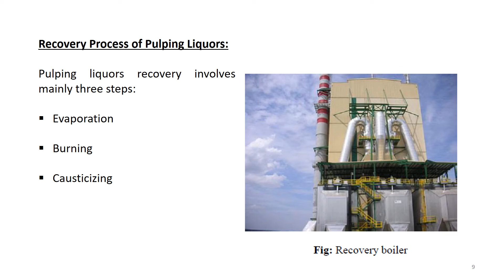As we have discussed, in the recovery process, or regeneration of pulping liquors, one of the main processes involved is evaporation. In the kraft process, weak black liquor is separated from the pulp by washing and sent to the kraft recovery system, where inorganic pulping chemicals are recovered for reuse, while dissolved organics are used as a fuel to make steam and power. So this evaporation step comes after the washing process, and we carry it out on the spent liquid.